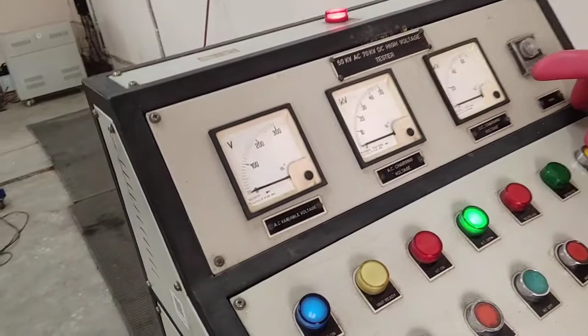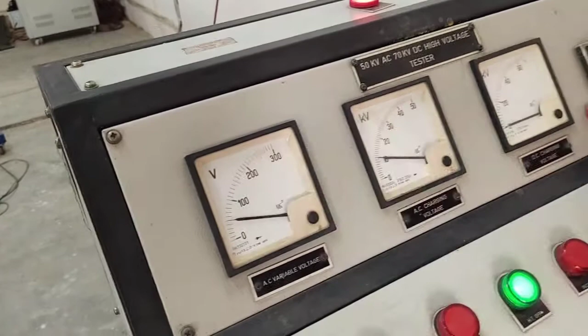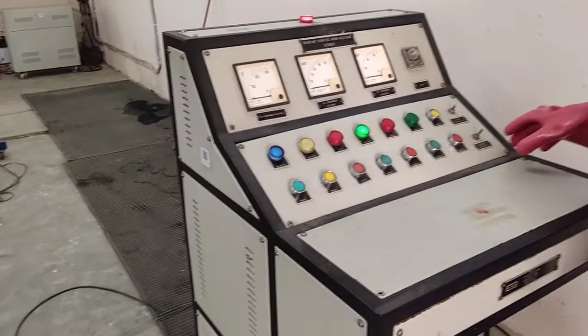The input voltage is increasing. Now you see the spark between the two sphere configuration. The spark occurs between the two. Now you want to see the breakdown voltage and then AC variable voltage. Press the memory push button. You see the voltage is 50 volt and then the breakdown voltage is 10 kV for 5 mm gap.